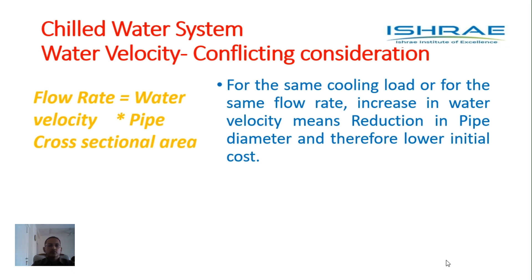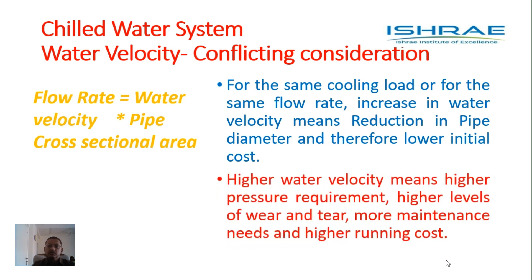Flow rate of chilled water is equal to water velocity multiplied by pipe cross-sectional area. We have already estimated what flow rate is needed based on the heat load. Higher velocity means lesser pipe cross-sectional area, means lesser diameter. Lower velocity means higher cross-sectional area, means higher diameter of pipes. So for the same cooling load or the same flow rates, increase in water velocity means reduction in pipe diameter and therefore lower initial cost. However, higher water velocity means higher pressure requirement, higher levels of wear and tear, more maintenance needs, and higher running cost.